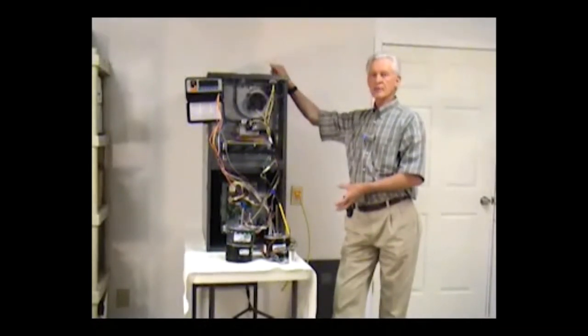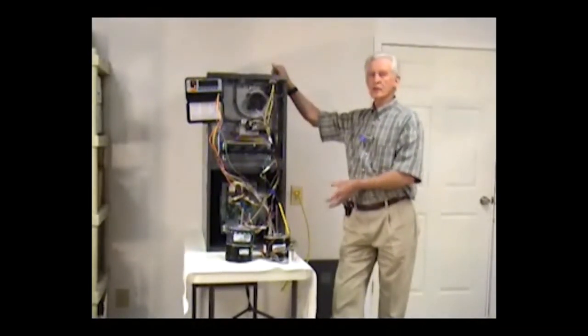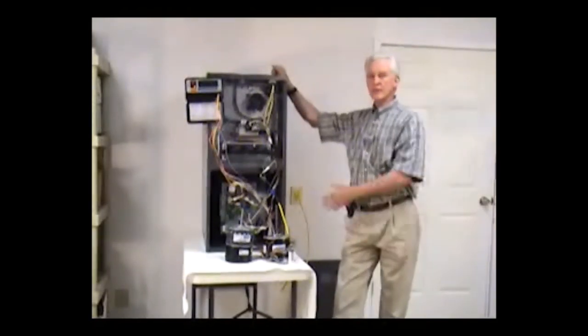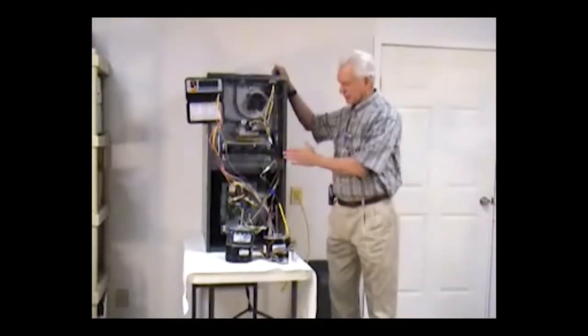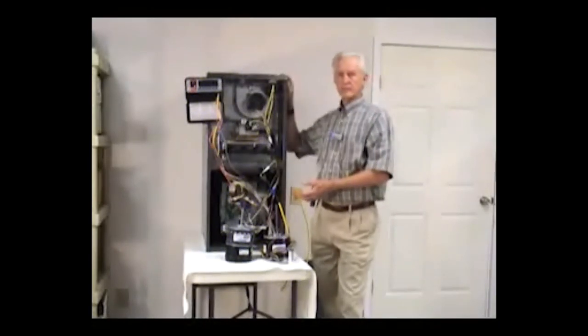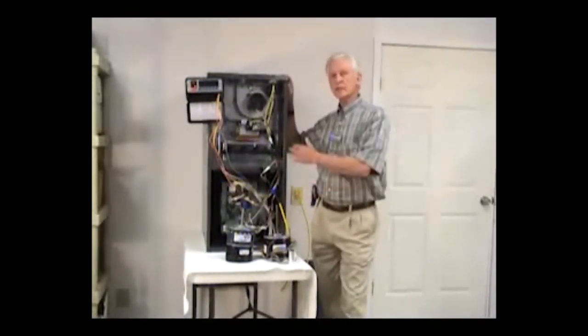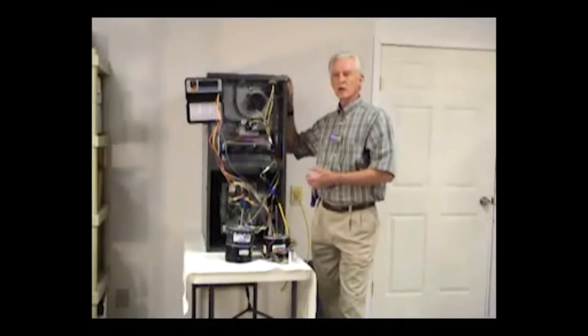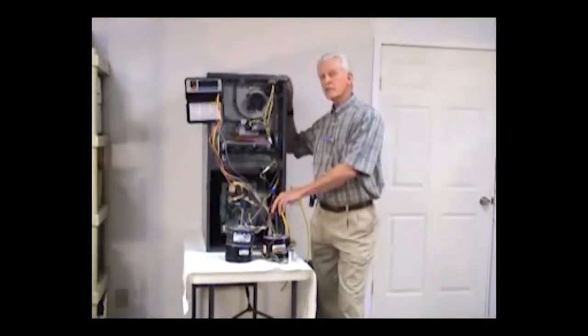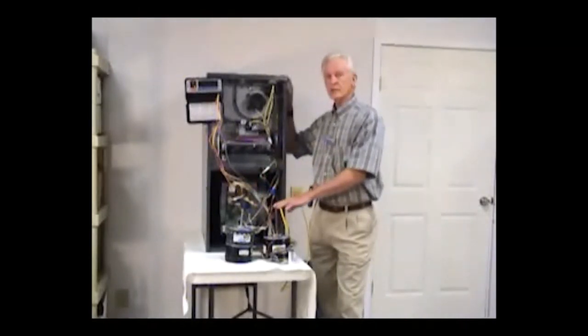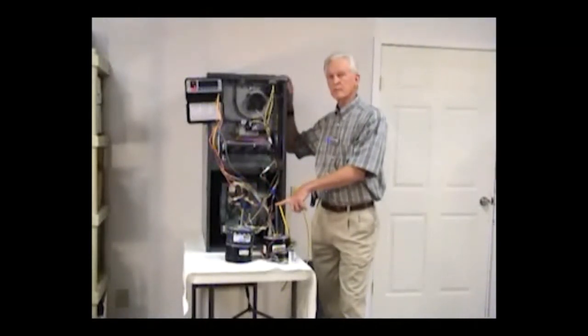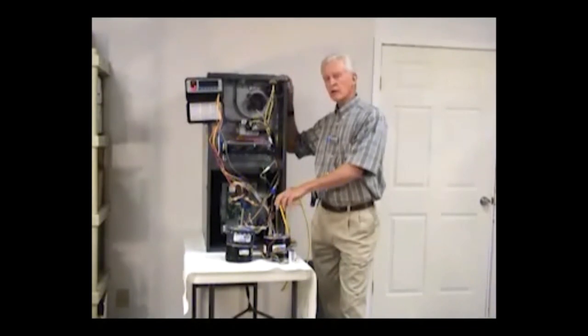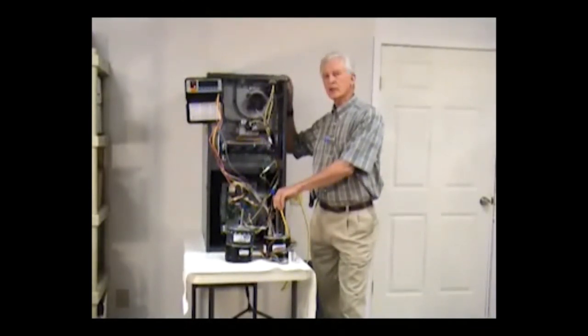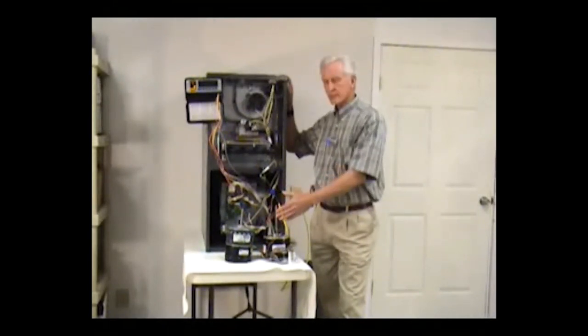The other thing that happens is an external part of the air handler or the air mover, in this case a gas furnace, is that you're going to put some type of filtering in. And all of these items that are external of the air mover are going to produce a resistance to airflow, which is the resistance to either one of these motors. In this case, we're talking about the PSC motor. When that occurs, lots of times we think in terms of the fact that this is a load against the motor, and that actually indeed it is.